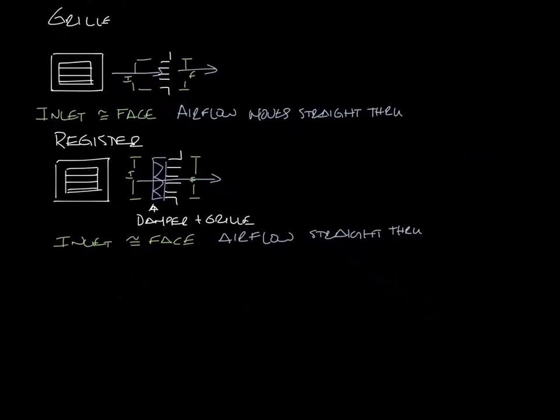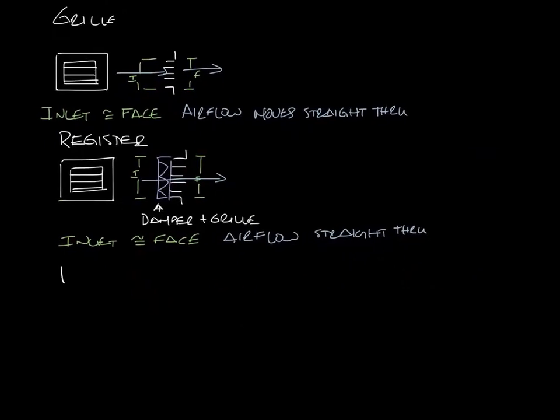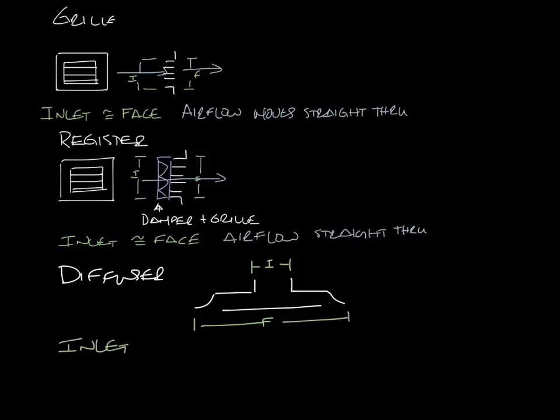Now diffusers. A diffuser typically looks something like this, where you've got the neck up here and then some sort of face plate. In this case, I'm drawing our omni diffuser. Your inlet or neck is smaller than the face of the diffuser. The airflow comes in at the neck and goes out along the ceiling, so the airflow makes a 90-degree turn and exits at a different angle than it came in.